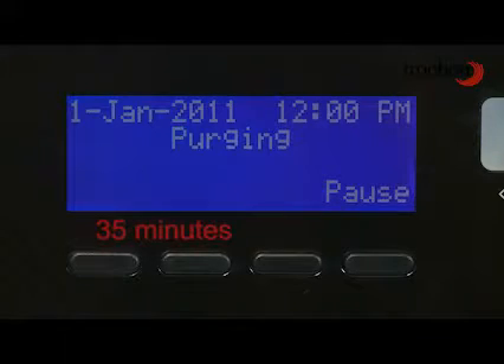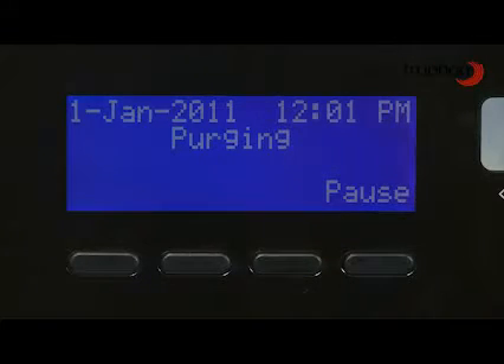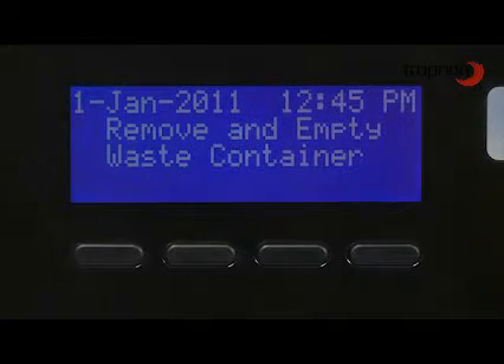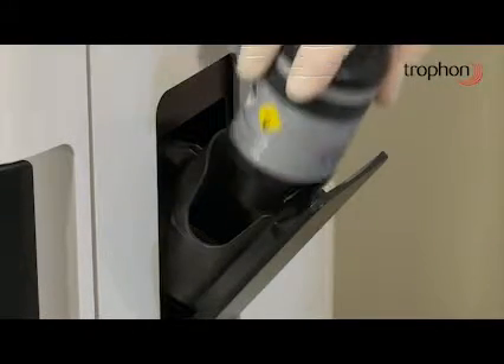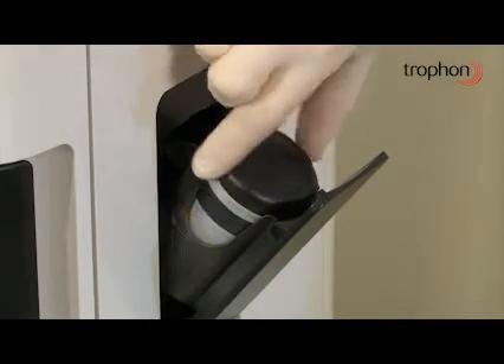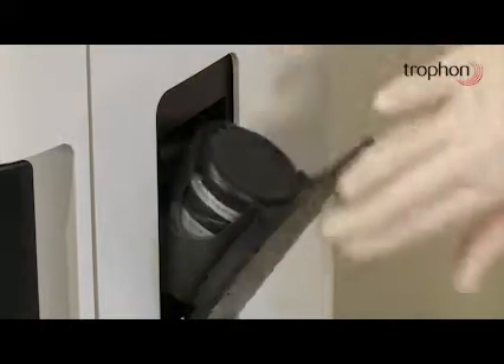A purge cycle typically takes 35 minutes to complete. During a purge, you may hear the sound of the pump pulsing, or the sound of a fan running in the background. At the end of the purge cycle, you will be asked to empty the waste drawer. Upon completion of a purge cycle, a new disinfectant cartridge will need to be inserted before you can commence a new high-level disinfection cycle.